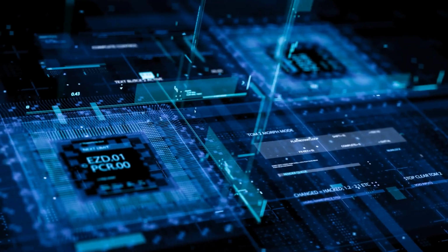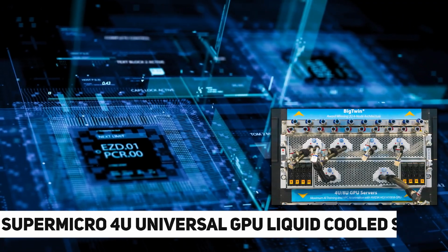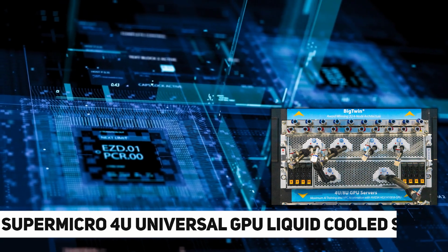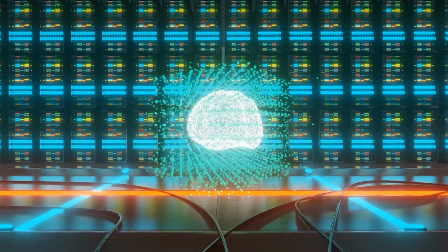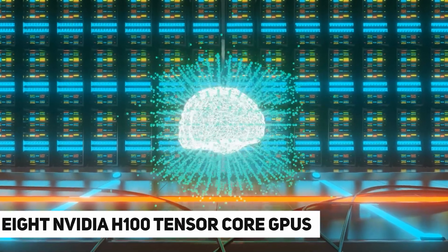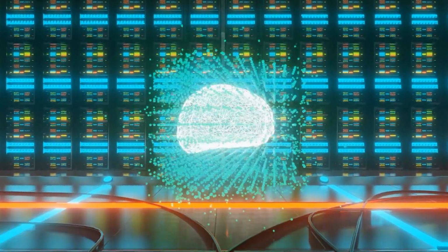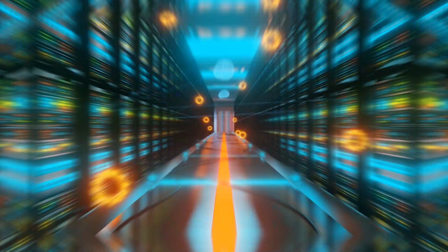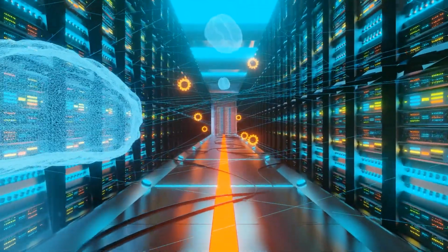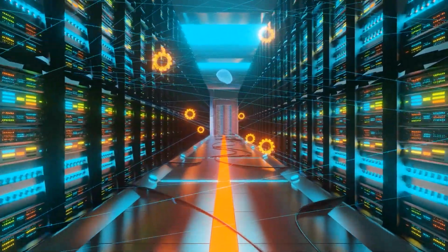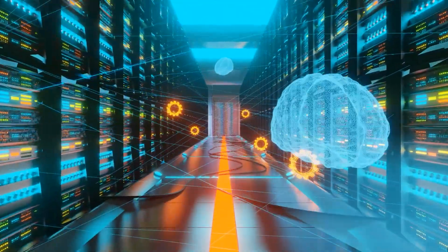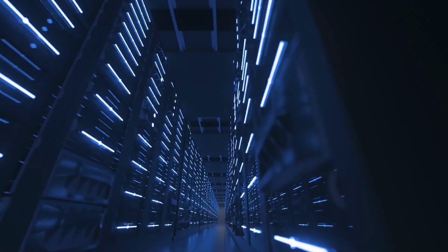Now, Colossus is built on a solid foundation, the Supermicro 4U Universal GPU Liquid Cooled System. Each 4U server in Colossus houses 8 NVIDIA H100 Tensor Core GPUs, packing a serious punch when it comes to AI training tasks. These servers are neatly arranged into racks, with each one containing 8 4U servers. That's 64 GPUs per rack. The cooling system is just as impressive. Between each server is a manifold that channels liquid cooling, taking up one unit of rack space, while the 4U CDU pumping system at the base ensures redundant cooling and smooth management.